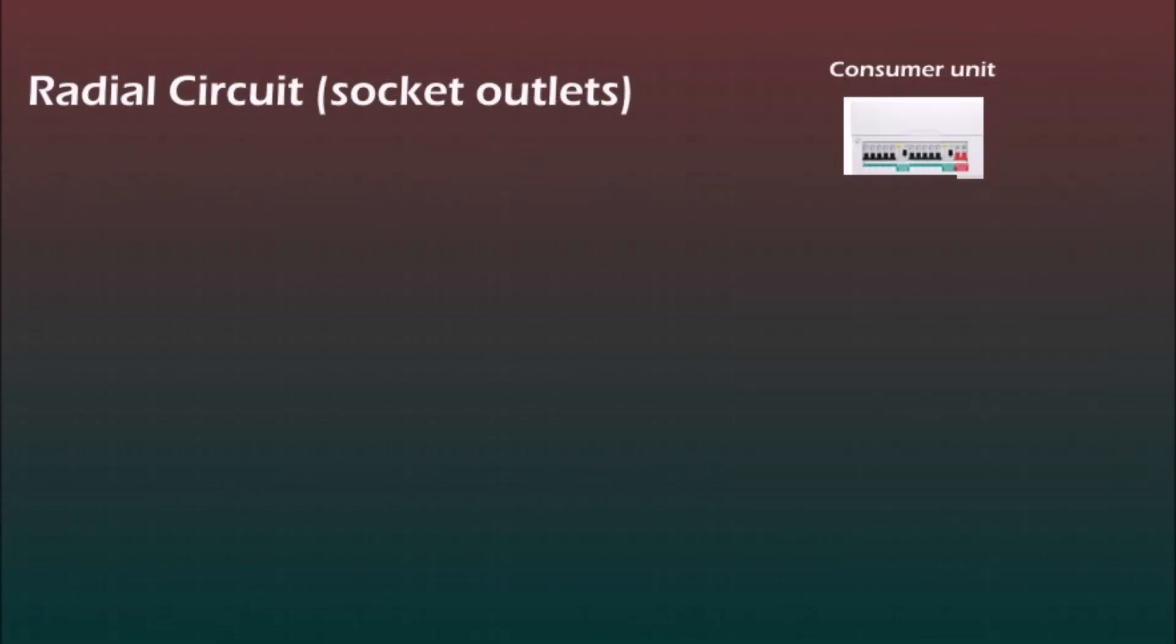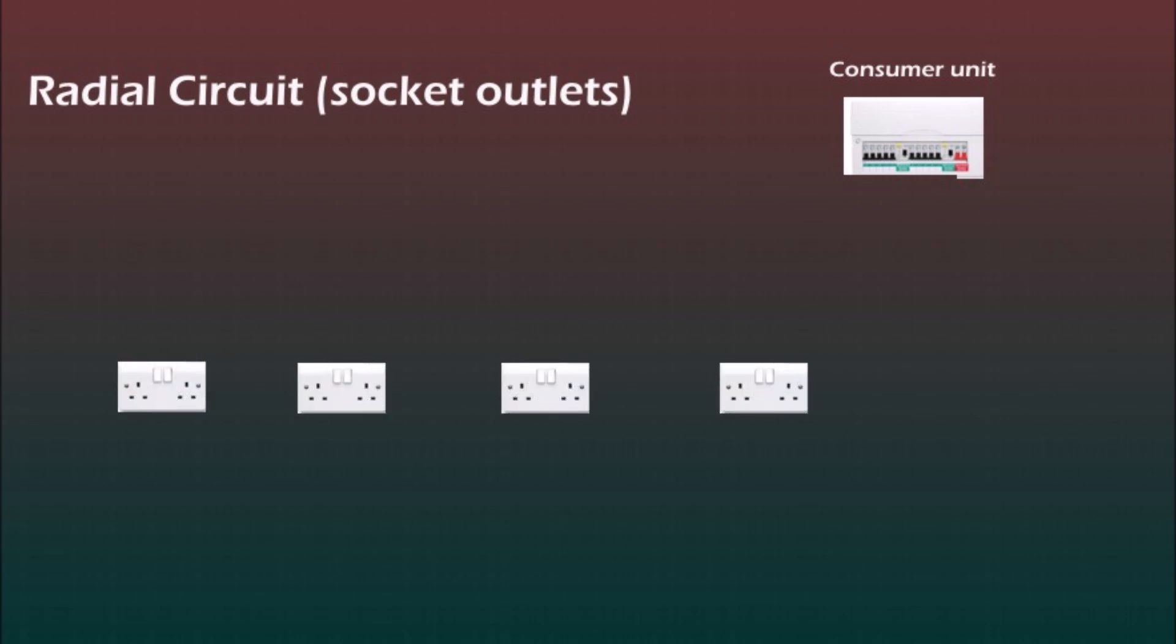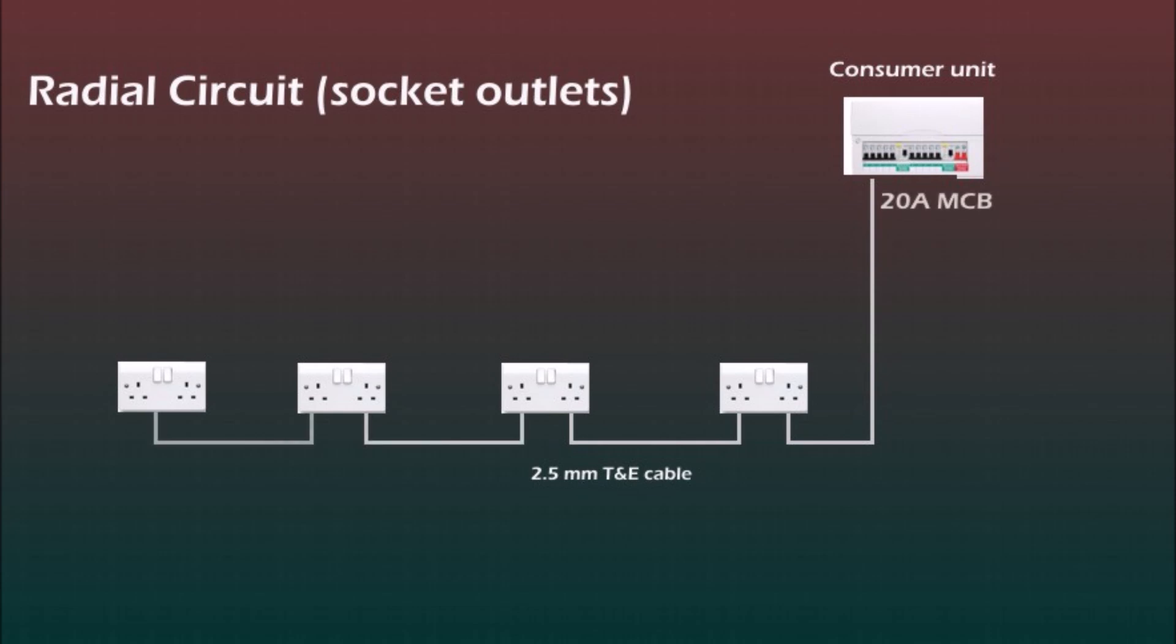So let's start with the simplest, the radial circuit for the socket outlets. On the top right corner you see a consumer unit and we've got four socket outlets on this circuit, so the 2.5mm twin and earth cable goes from consumer unit to the first socket outlet and turns from the first to the second and so on and it finishes at the last socket outlet. The MCB for this radial circuit should be 20A.